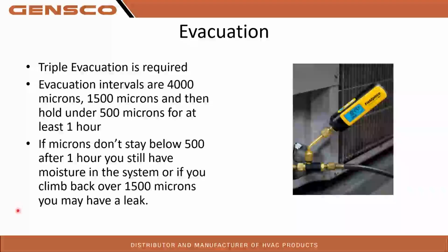So for the first interval, like I said, once you hit 4,000 microns on your gauge, you shut your gauges off, then shut your pump off. Then add nitrogen into that system until you get back up to 0 psi or so. You don't need to go crazy and go super high with pressure. Once you get back up to 0, you open your gauges back up and turn your pump back on. Next, you're going to pull it down to 1,500 microns, and then do the same thing. Break your vacuum with nitrogen, bring it back up to 0, and then put it back on vacuum again. And then you should get under 500 microns.